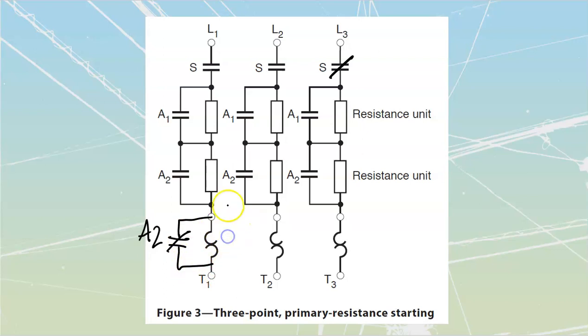So if I would take an A2 normally closed, anytime that A2 has not operated yet, which means that we haven't gotten to our full running stage, I would therefore be able to pass current through. So if I'm in startup, I would be able to pass like that around there. If I'm in step 1, that would mean I'd have closed this one over here. Then I would have current going through like this.